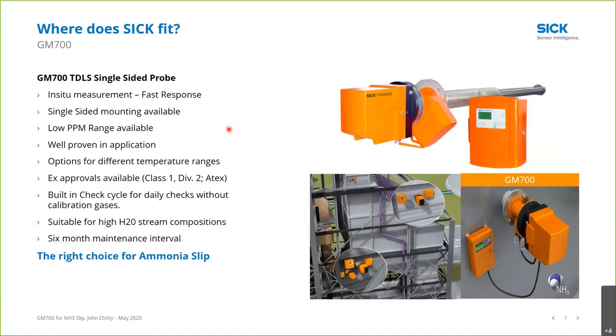It is available for hazardous areas for Class 1 Division 2 and ATEX. It has a built-in check cycle for daily checks. It's suitable for stream compositions with a lot of water, and it has a 6-month maintenance interval, so it's low maintenance as well. It's a pretty good choice for ammonia slip.